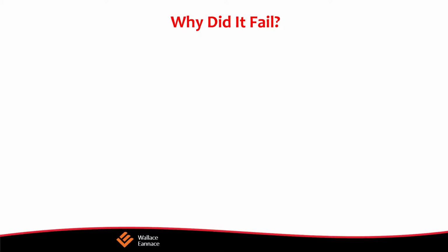As you can see, looking at an old boiler, with an old system you had high maintenance costs, you have high losses, standby and surface losses, high temperature flue gases, which is basically throwing energy out into the atmosphere. There are inefficient system controls that leave you with hot and cold spots and also don't maximize the operation of the boiler. And also you have high emission levels, large NOx, carbon dioxide, and carbon monoxide.